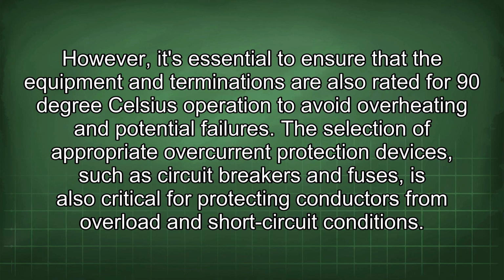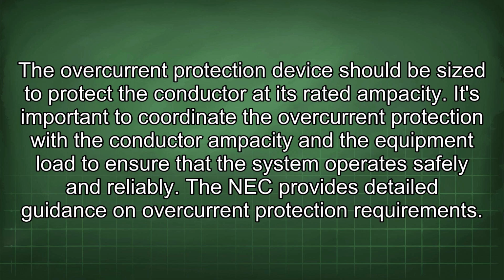potential failures. The selection of appropriate overcurrent protection devices, such as circuit breakers and fuses, is also critical for protecting conductors from overload and short-circuit conditions. The overcurrent protection device should be sized to protect the conductor at its rated ampacity. It's important to coordinate the overcurrent protection with the conductor ampacity and the equipment load to ensure that the system operates safely and reliably.